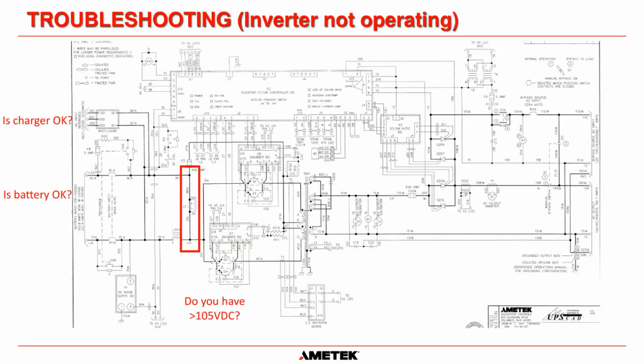Well, what can go wrong? Okay, so the first thing that we're going to look at is, okay, the inverter's not operating. The inverter is not running. And on the Micro-ferro, they make a humming noise when they're on. So you should be able to hear that. And obviously the common alarm should not be on. So if the system is on bypass and the inverter is not operating, there's a few things that you can check. Okay. And the first thing is, do you have greater than 105 volts DC going into these 2 points here? And that's basically directly across the capacitor bank that's connected to the inverter bridge.